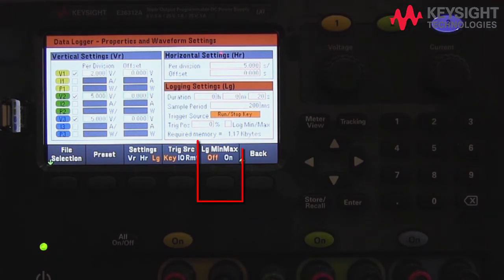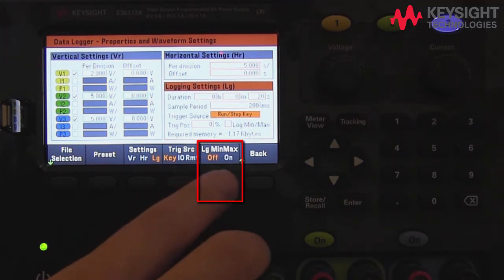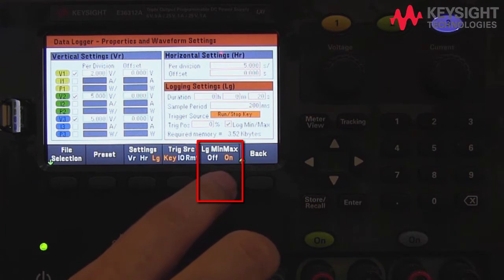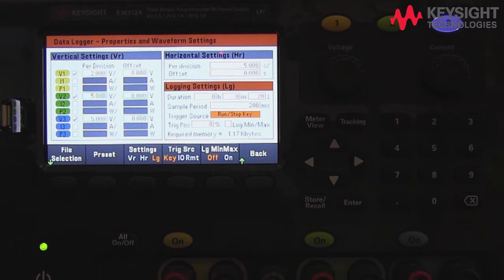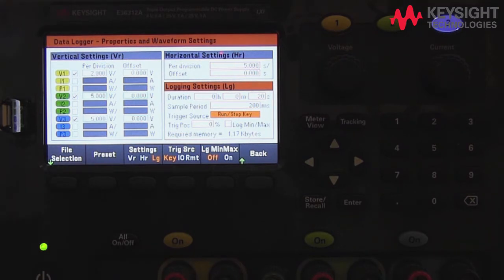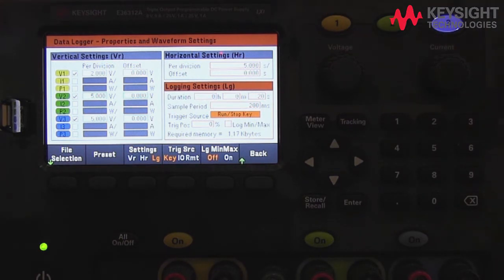We can also set the log min/max value. When this is enabled, the minimum and maximum value will also be recorded. Note that this will triple the file size, as you can see from the required memory. Bear in mind that you can't exceed 7 MB. Size is dependent on the configuration selected, such as the number of traces, duration, and sample period.